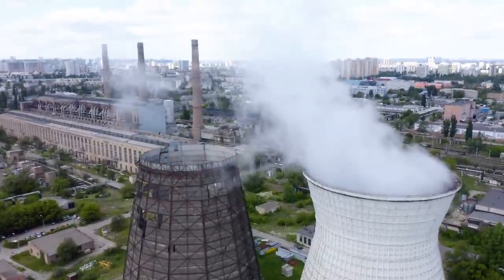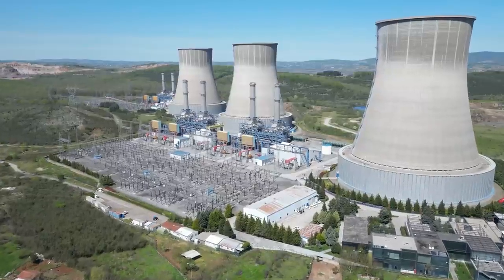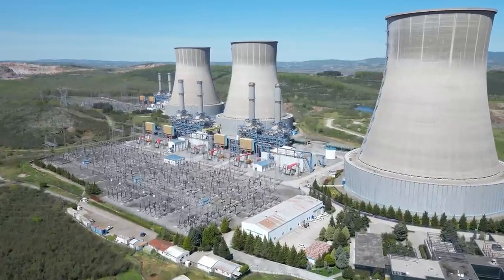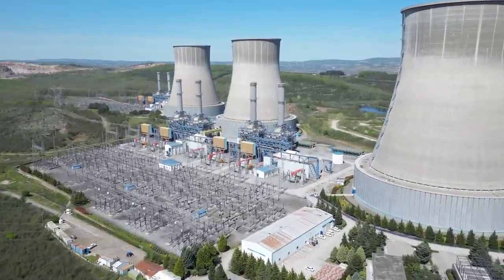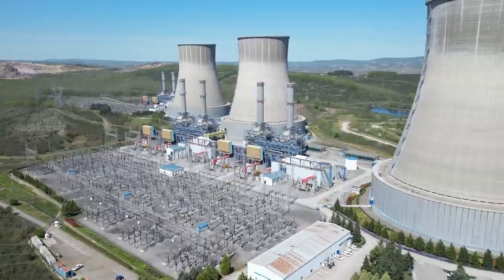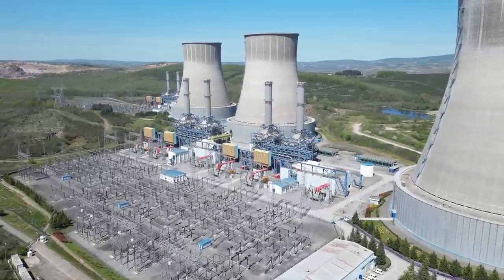The reason you see big natural draft towers at power plants has everything to do with scale. The long-term savings of not having to run big fans and maintain all the associated equipment outweigh the higher initial costs. Particularly at nuclear plants built with design lives of 50 years or more, you can amortize the cost over a longer duration. Also, these facilities are usually already built in more remote locations where land is cheaper and height restrictions are less stringent, making it feasible to build such massive structures just for cooling.